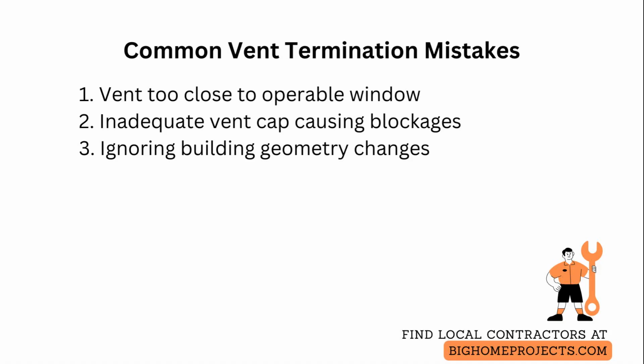the applicable local requirement. A second issue is using an inadequate vent cap that traps debris or permits pest entry, which causes odors or blockages. Replace with a properly sized screened cap made of durable material and check it during routine maintenance.